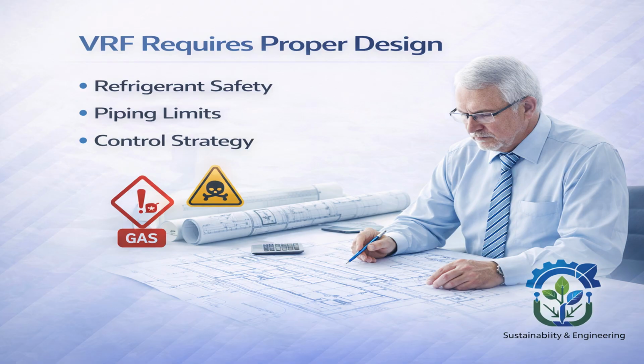The third is control strategy. VRF systems depend heavily on controls. Without a clear control strategy, indoor units fight with each other, energy efficiency drops, and occupants complain. Controls must define how zones operate, how schedules are managed, and how part load operation is optimized. In hotels, offices, and mixed-use buildings, good controls are the difference between success and failure. So, VRF is not a copy-paste system. It is a design system. When refrigerant safety is checked, piping limitations are respected, and controls are clearly defined, VRF performs beautifully.